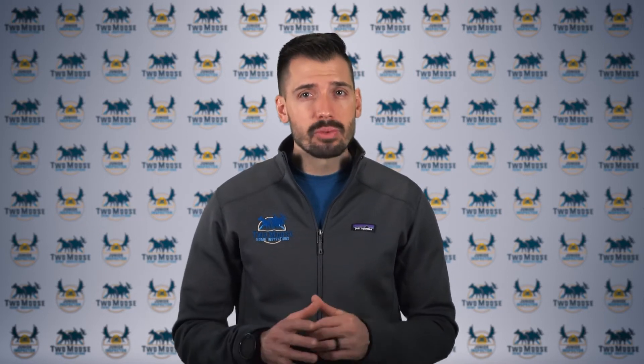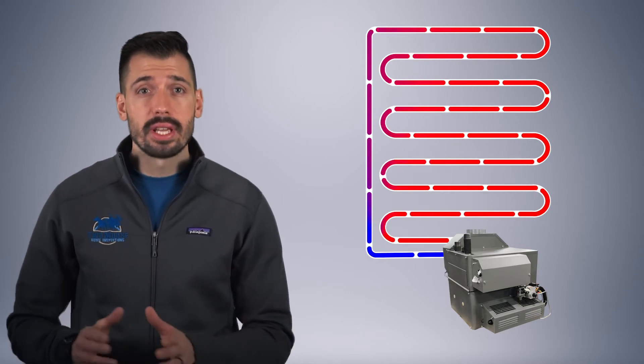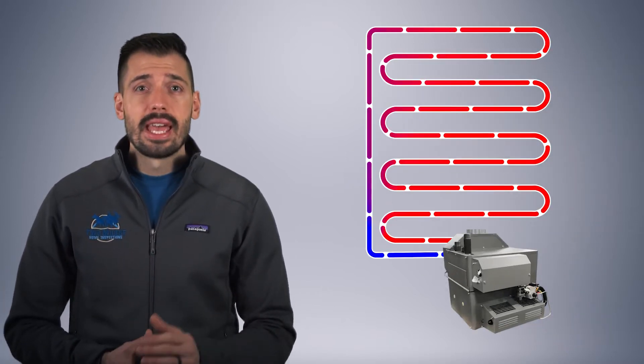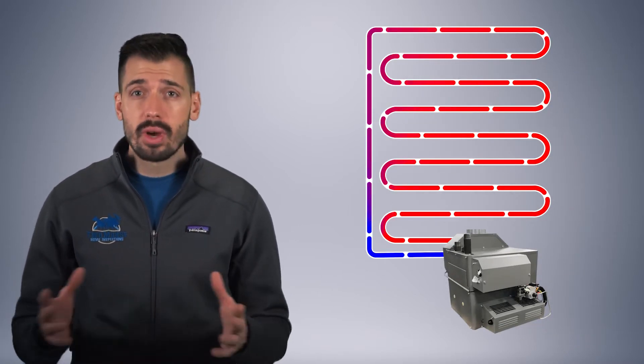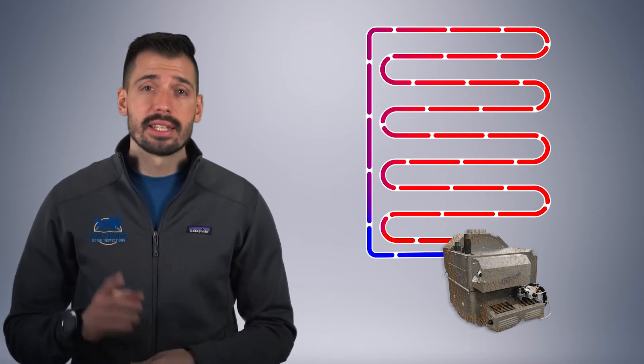Here's the one sentence recap from video one. Some homes had hydronic heating systems such as in-floor radiant heat or heated driveways that were installed with oxygen permeable pipe that allowed oxygen to diffuse into the closed loop hydronic system and caused the components of the system to rust away until nothing was left except a prematurely failed system that needed to be replaced at great expense.